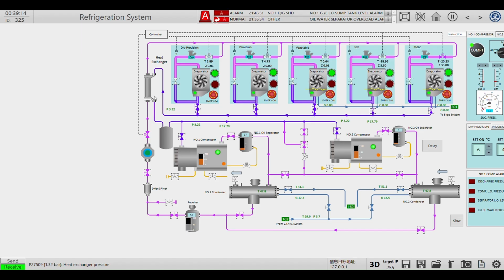So what it's doing here is subcooling the liquid refrigerant going to the evaporators. So this will give its heat, and this will take the heat from the liquid refrigerant. So it will do some degree of subcooling here and it will get heated, so the degree of superheat will increase, and then it will go to the compressor.